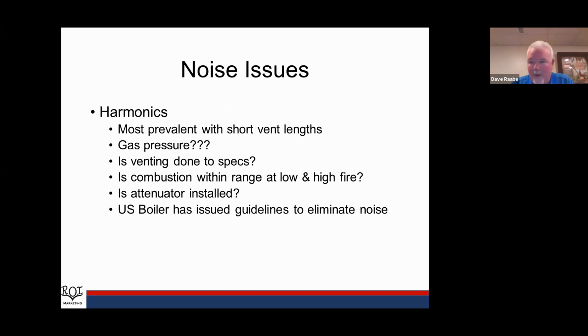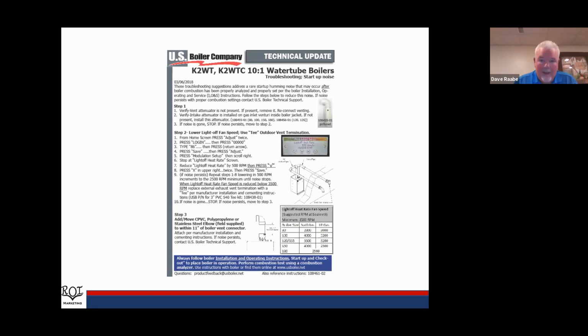US Boiler has actually put out a technical bulletin on eliminating noise. They actually have one done up for the water tube boilers that shows you how to make the adjustments. We can actually adjust our light off rate in increments, and verify that our venting's correct and that we do or do not have a noise attenuator involved. If you run into noise issues, I suggest getting a hold of somebody at ROI or call the tech line at the factory. Not something that we want you to spend a lot of time messing around with. We've run into some of these, and we're pretty confident we can walk you through this.